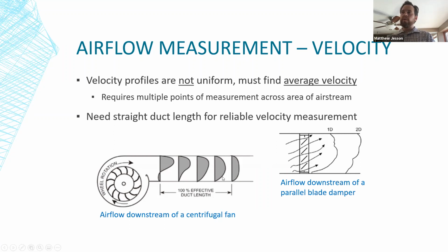As it gets further down, it starts to even out. But even once it's fully developed flow, it's not just straight down. It's not all equal velocity all across the area, because the sides of that airstream kind of stick to the duct, and it creates that kind of D shape. So you need to take an average velocity, taking all of that into account. The other diagram there with a parallel blade damper that's about halfway open is very similar to the fan. It pushes all the velocity up to the top of the duct, and you get turbulence downstream.